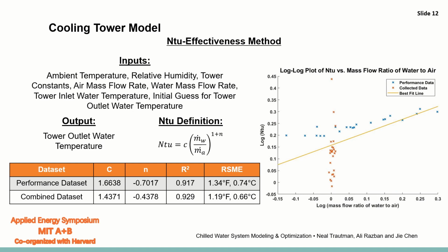So instead, we had to use performance data that was published for the cooling tower that we were taking data from. The performance data was published by the Baltimore Aircoil Company, and you can see in the graph on the right that we used a combination of both performance data and data that we collected from the system. The advantage to using both pieces of information was that we were able to actually increase the R squared and RMSE of our relationship, improving the accuracy of our model, because when we used the performance data alone, the NTU of the cooling tower model tended to be overpredicted.